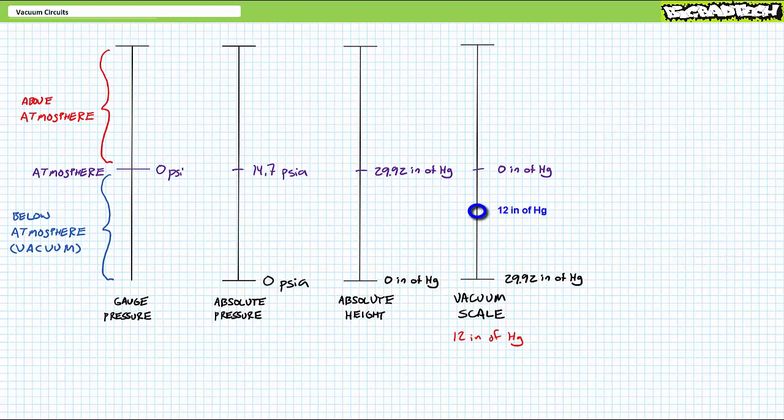Let's say we've got 12 inches of vacuum expressed using the vacuum scale. And we want to express the same value using the absolute scale. This takes a couple steps. Vacuum scale to absolute height scale, then absolute height scale to absolute pressure. To convert from the vacuum scale to absolute height scale, one needs to flip-flop the reading. 12 inches of vacuum means the 30-inch column of mercury moved down 12 inches, thus 30 minus 12, or 18 inches remains.